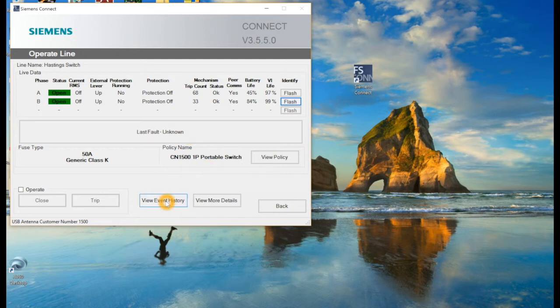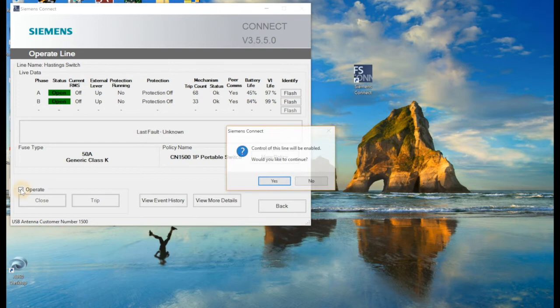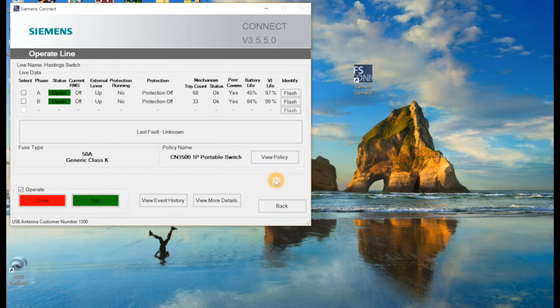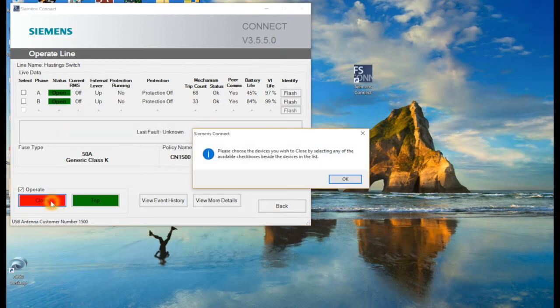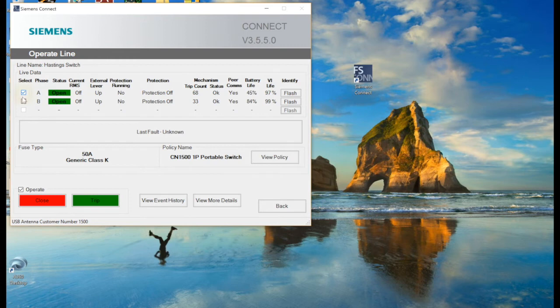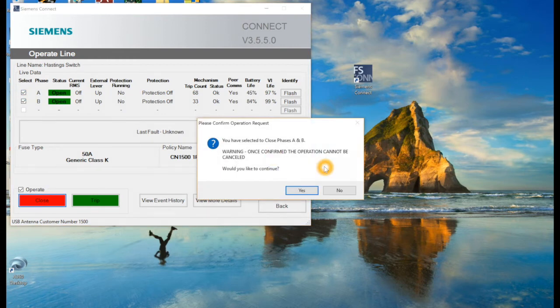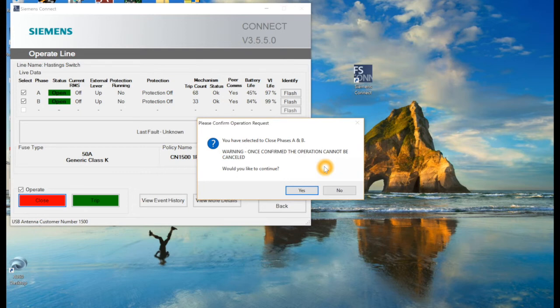Moving on here, let's get into the operation. Now when you're ready to operate these switches, I've got both open, I want to close them. I'm going to click this little box here, operate. It says control of the line will be enabled. Now again, they're open, I want to close them, so click close, please choose which devices. So you're going to choose both devices. I want to close both devices, click that, and it says once I have confirmed I will not be able to cancel these operations wirelessly. So that's, I cannot cancel them from my laptop. If they need to be canceled for safety purposes or any reason, they will need to be, that safety release lever or latch will need to be physically pulled on both units. So you can't do that from the wireless feature. Go ahead, click yes.